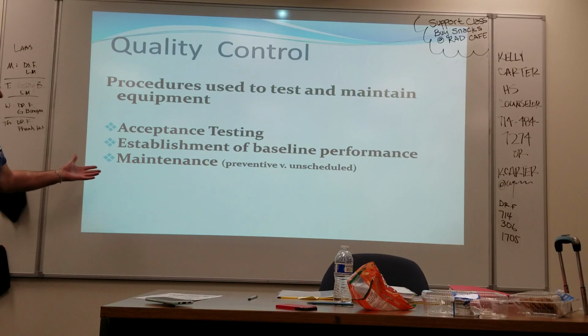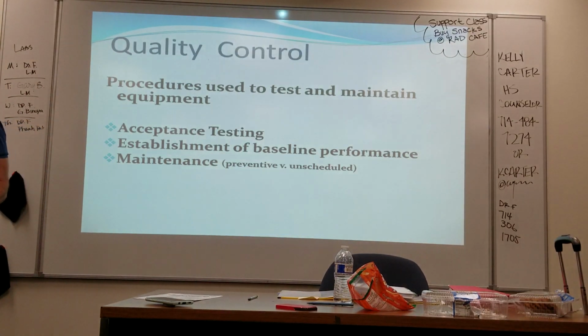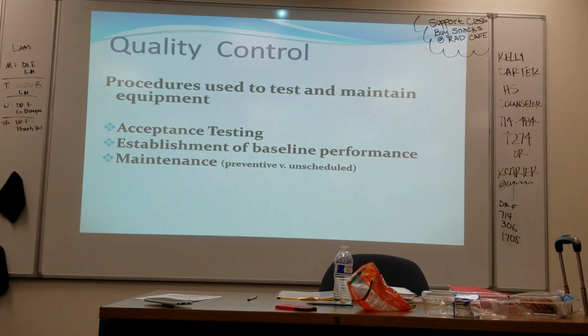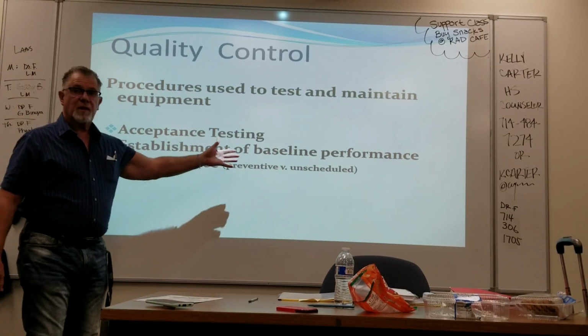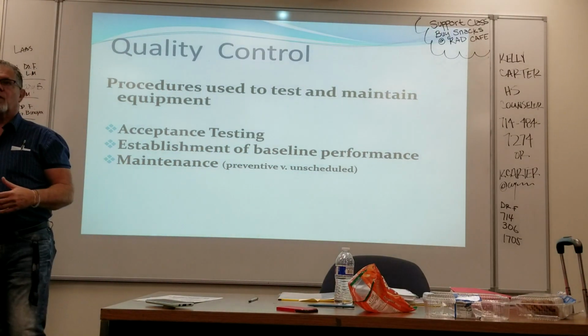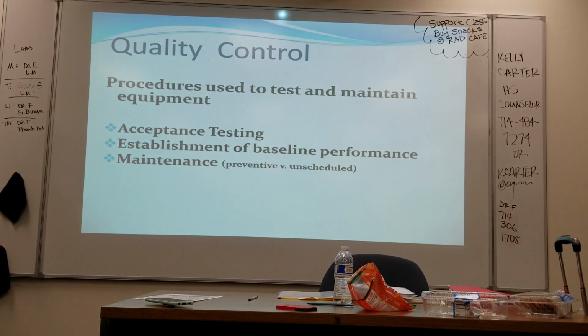Maintenance, you have preventive or unscheduled. Unscheduled, that's what it's called when something breaks. And that includes everything, even down to the fact that your collimator light goes out. That's an unscheduled maintenance.